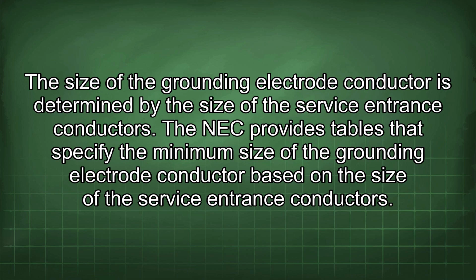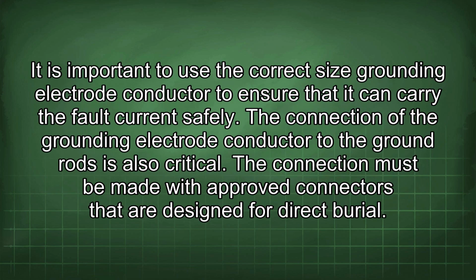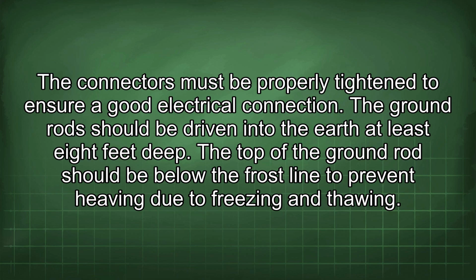The NEC provides tables that specify the minimum size of the grounding electrode conductor based on the size of the service entrance conductors. It is important to use the correct size grounding electrode conductor to ensure that it can carry the fault current safely. The connection of the grounding electrode conductor to the ground rods is also critical. The connection must be made with approved connectors that are designed for direct burial. The connectors must be properly tightened to ensure a good electrical connection.